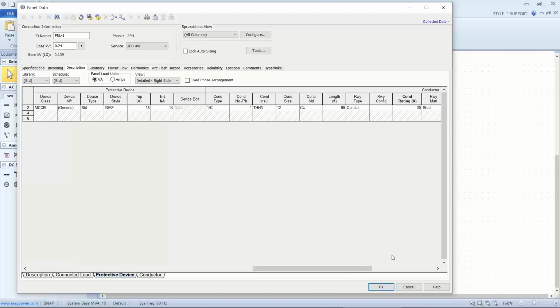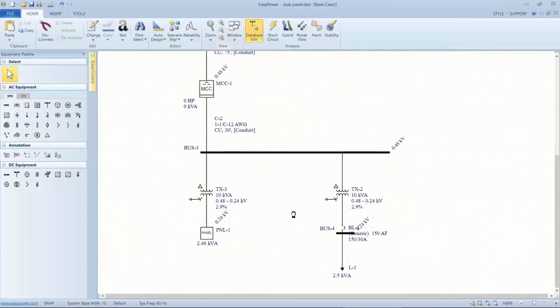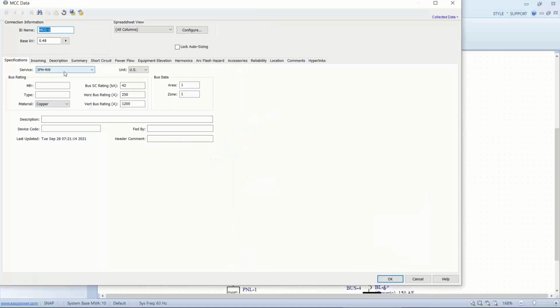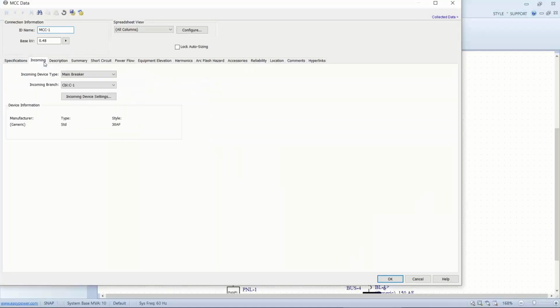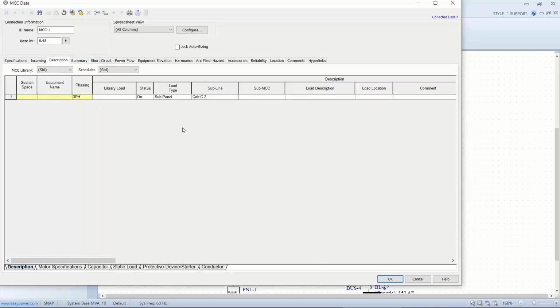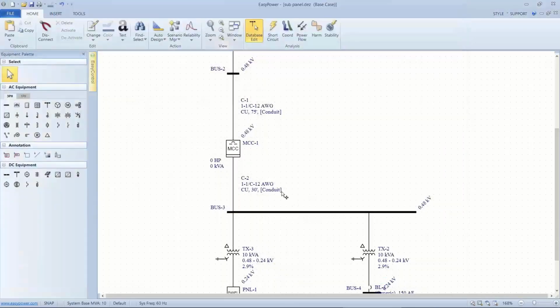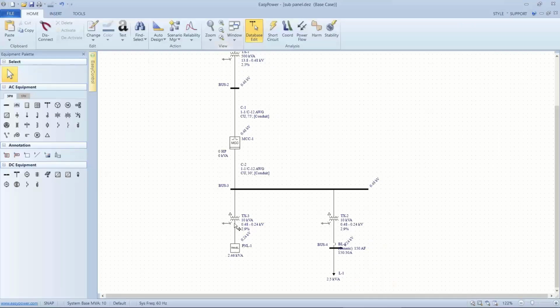And the rating is in the device library. If I go back to here, the reason for the cable errors was I wasn't connecting the incoming as it should be. So we're having a standard 30 AF for the main, and then for my load, we're getting a standard 150 AF. So it's sized according to the new rules, the area that I had a problem with to start.